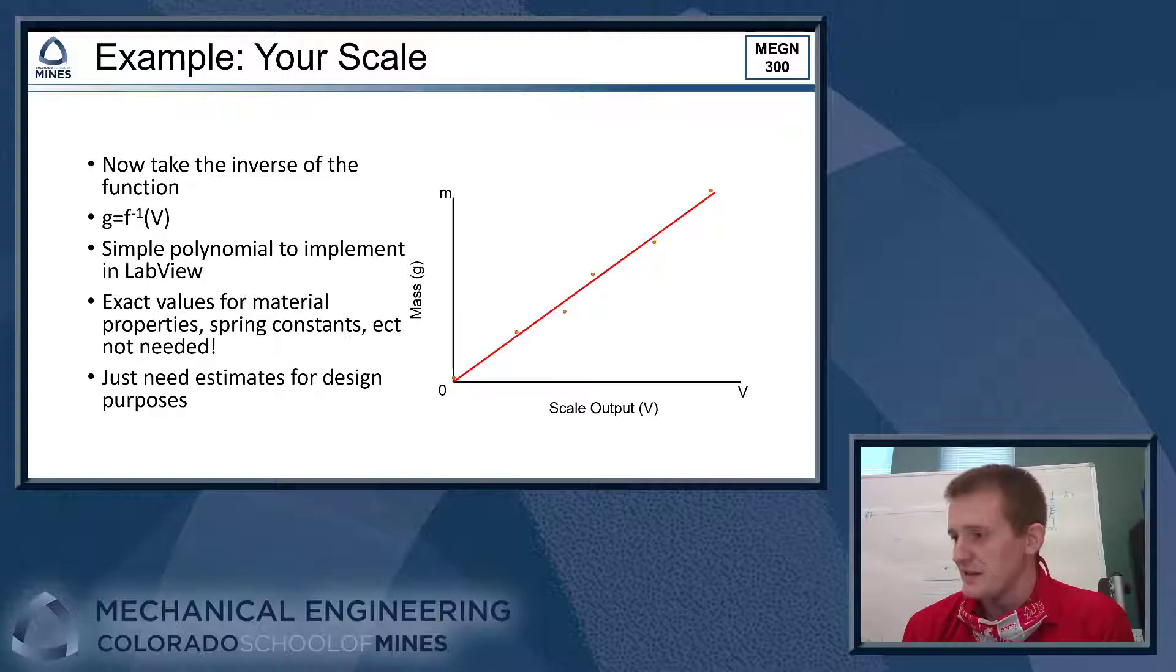So the reason why we've been estimating those in class and kind of working through that is it's important for your design work so that you can verify that your scale will work ahead of time. You can basically ballpark, you know, this is effectively what the scale should do when I build it. As long as I see something close to this, I have confidence that my scale is working properly. That's why we go through that exercise. It's important. It saves you a lot of time and heartache in the lab because you know what you're looking for. And if you get something that's significantly different than that, you know your scale is not working and it helps guide your troubleshooting. But having that experimental calibration curve makes it much, much easier to program your scale so that it will output mass in grams to the front panel of your VI.